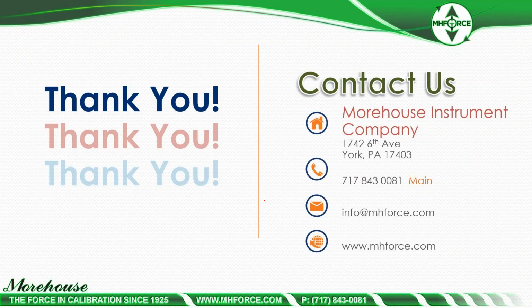And in the end, if you're not sure, somebody may have that question. I'm just not sure how good my machine is. Participate in a PT test, have 2 load cells calibrated in dead weight and compare them against each other, have 2 torque cells calibrated or a torque cell calibrated and compare it against another one. See if you get the right answers. Use the company that's going to give you the right answer, and then test your machine and see what you get in your machine.